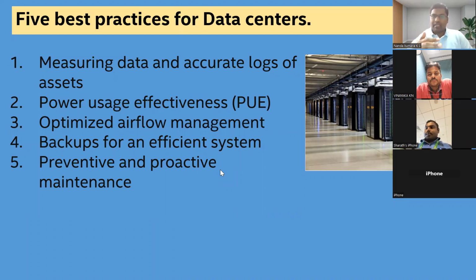In terms of HVAC, a precision air conditioner shows supply air temperature and return air temperature. In case of a DX unit, the line pressure. In a chilled water system, inlet water temperature and outlet water temperature. There are different kinds of parameters, and generally a PAC will show 12 to 18 parameters. Not all parameters are very critical, but at least 10 to 12 parameters should be recorded. That data should be accurate.